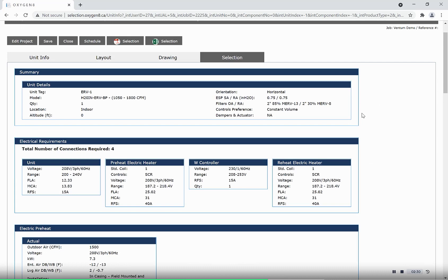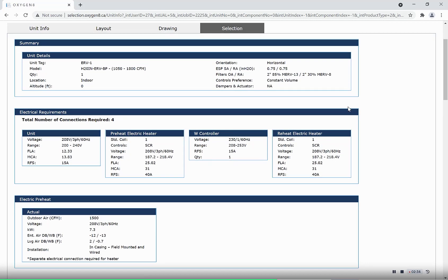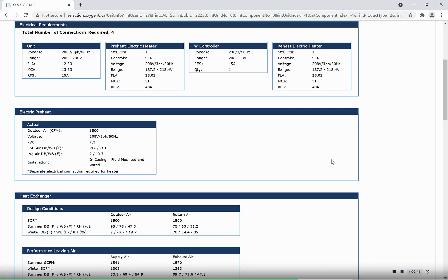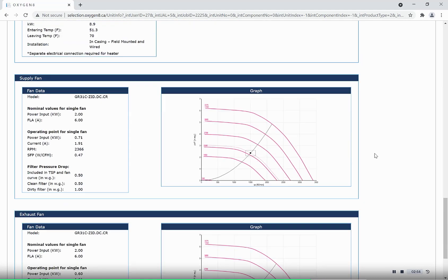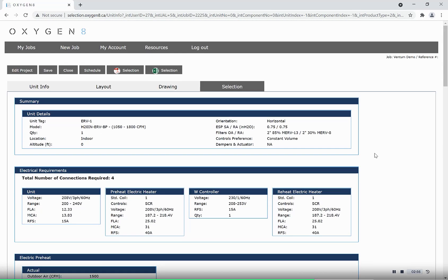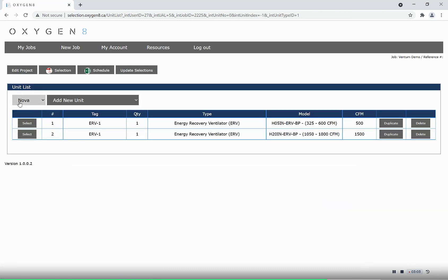The selection tab shows you the output from the ERV. At the top is your unit information. Next is your electrical connections. Note that all electric heaters, as well as the W controller for the DX integration, require a separate electrical connection. The preheat will be automatically selected to prevent any frost from forming across the core. Your heat exchanger and coil data follows. From here you can click Select, which will give a PDF output, or you can go back to the schedule page to add another unit.